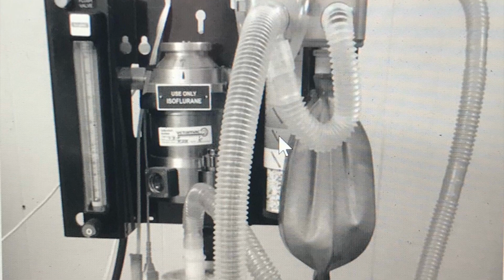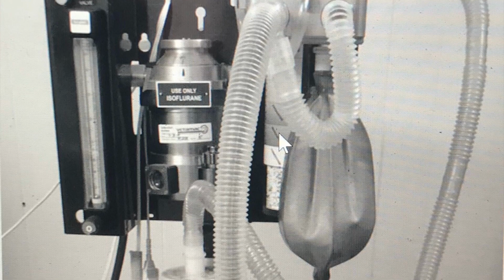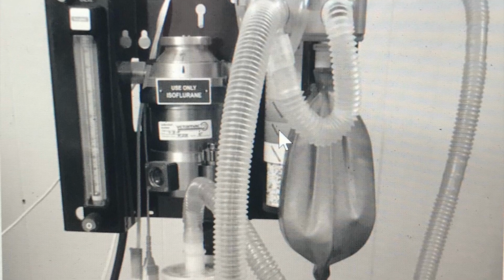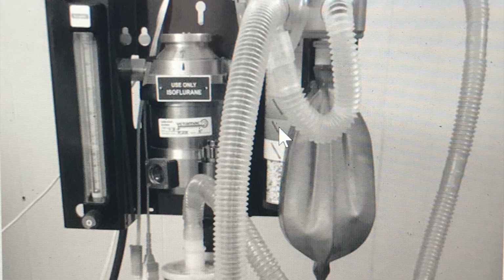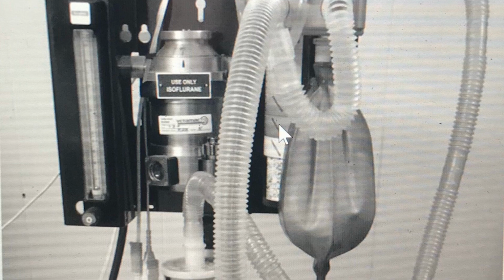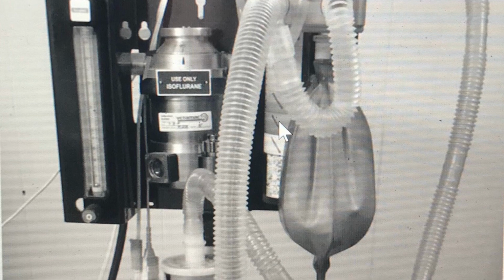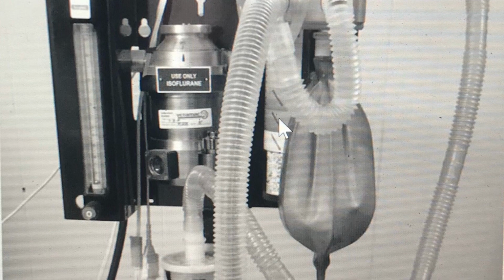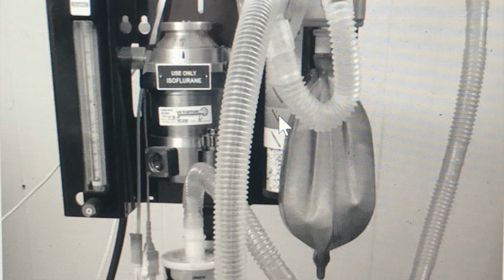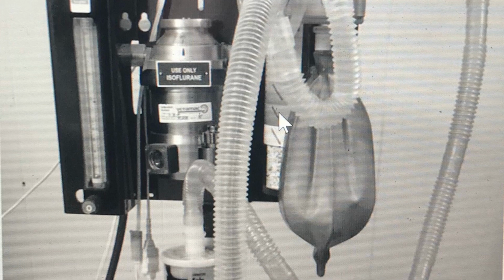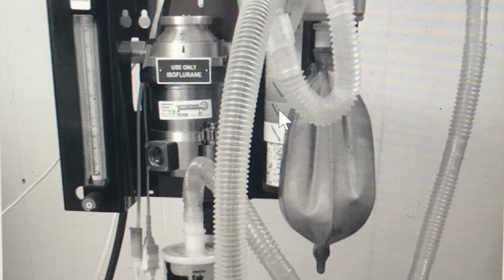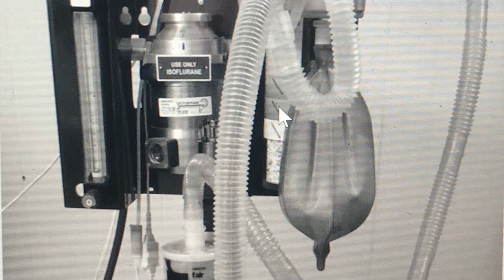Once you've done that, you will check your CO2 absorber, and sometimes if it has been exhausted, it will turn blue or purple. If this is the case, you must remove it and refill it. If there is no dye, then you must take a piece of the absorber and break it. It should break and crush fairly easy, and if it doesn't, then it should be changed before your procedure. You're now ready to check your system for leaks.